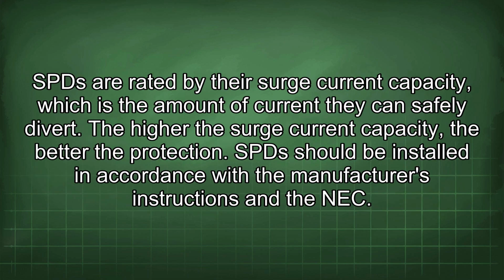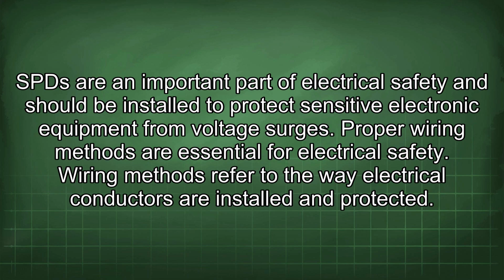SPDs are rated by the surge current capacity, which is the amount of current they can safely divert. The higher the surge current capacity, the better the protection. SPDs should be installed in accordance with the manufacturer's instructions and the NEC. SPDs are an important part of electrical safety and should be installed to protect sensitive electronic equipment from voltage surges.